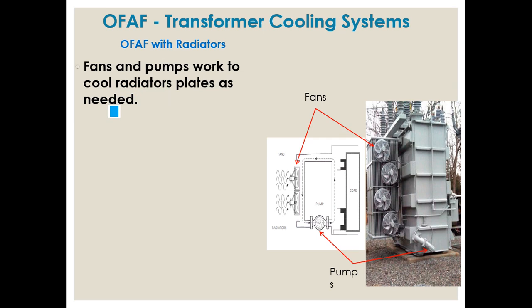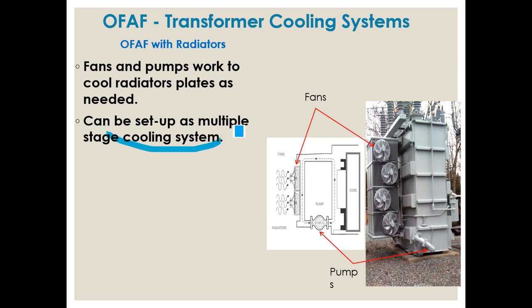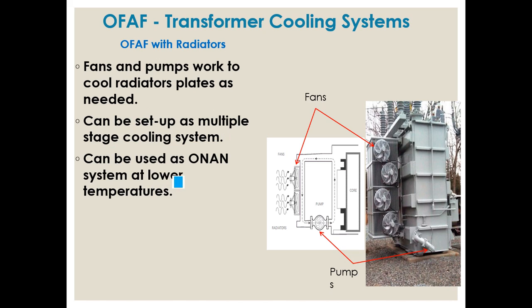The radiators will be cooled by fans in a multiple stage cooling system - one side radiator may be cooling at a different stage, so it will be multi-stage. The OFAF transformer at lower temperatures can also be used as ONAN - oil natural, air natural - by switching off the fan and the pump.